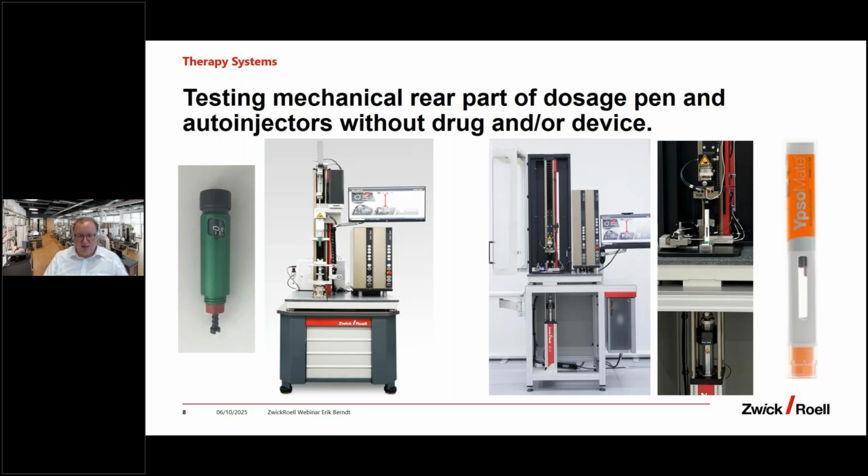Originally, this idea came from the device producers, as they do not have access to the drugs. They have only perhaps some water displacement and so on. With this, we developed years ago already this mechanism where we look at the mechanical rear part, the functionality, and can prove that all this works, that in the pen, the plunger rod movement is fulfilling all the rules. And at the end, if you have the movement of the plunger rod multiplied with the area, this would be also like the volume ejected.